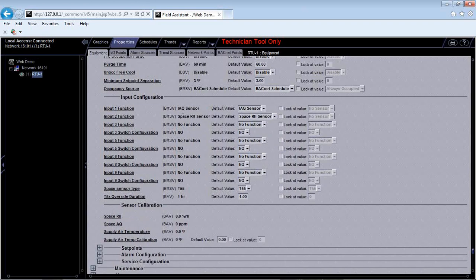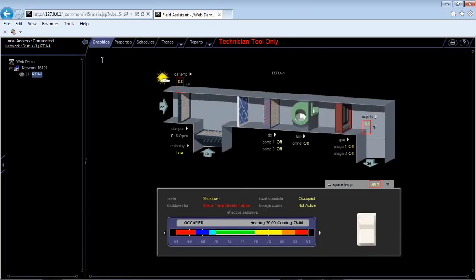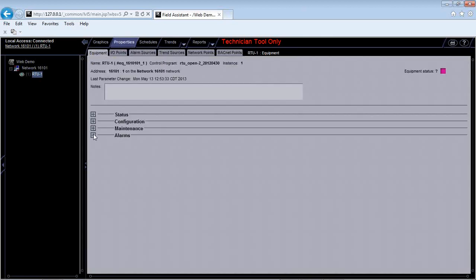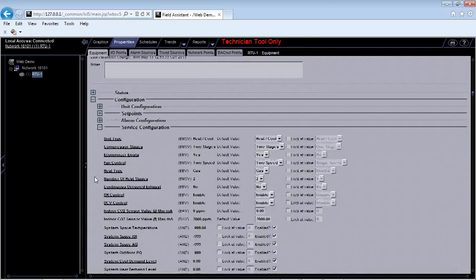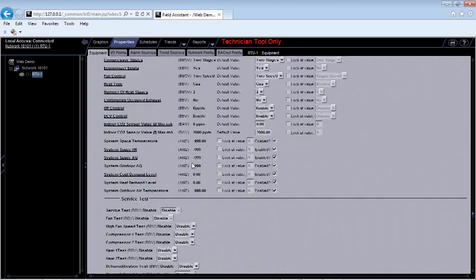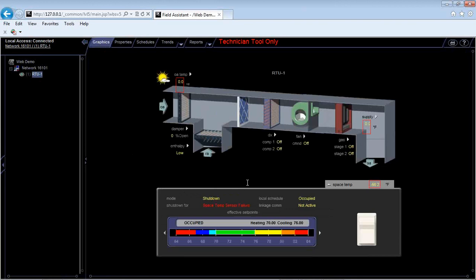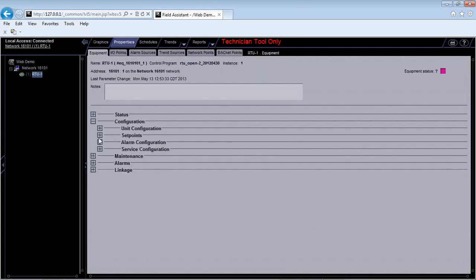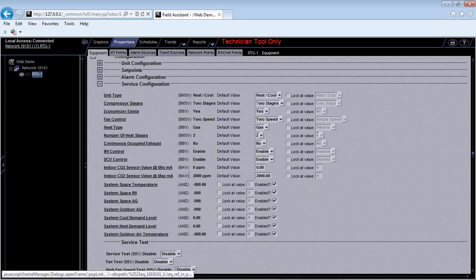So I hit OK. Now if I look at my graphic, it should show up with it. Let's go back here real quick. Made my first mistake, guys. Sorry. It says I have relative humidity control. It should show up with reading parts per million on this graphic. Well, I'll have to double check it. Maybe this unit needs to be updated with the newest driver, but it should show an IAQ of parts per million of 0 right now because I don't have that, and you should be able to see a space relative humidity as well. So I must be doing something wrong here. But if I go back to service configuration, you can see you can actually read your range for 0 parts per million to 2,000 parts per million of what your sensor can read.